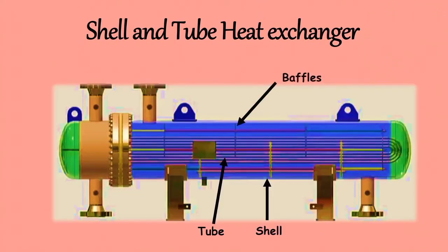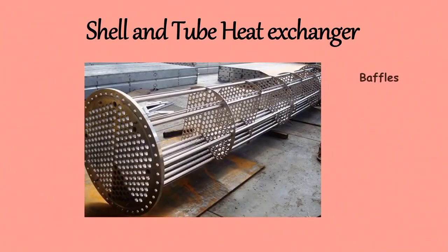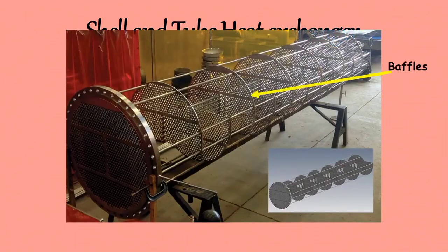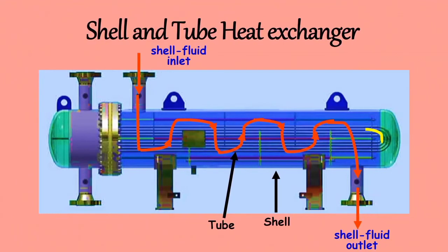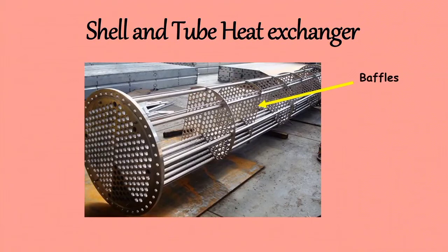The next component is Baffles. Baffles are commonly employed within the shell of a heat exchanger to increase the rate of heat transfer by increasing the velocity and turbulence of the shell side fluid. They are also used for structural support for the tubes and as dampers against vibration. The baffles cause the fluid to flow through the shell at right angles to the axis of the tubes. To avoid bypassing the shell side fluid, the clearance between the baffles and shell, and between the baffles and tubes, must be minimum. The center-to-center distance between adjacent baffles is known as baffle spacing or baffle pitch. Baffle spacing should not be greater than the inside diameter of the shell, and not less than one-fifth of the inside diameter of the shell. The optimum baffle spacing is 0.3 to 0.50 times the shell diameter.